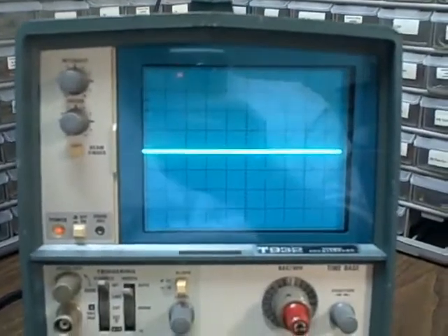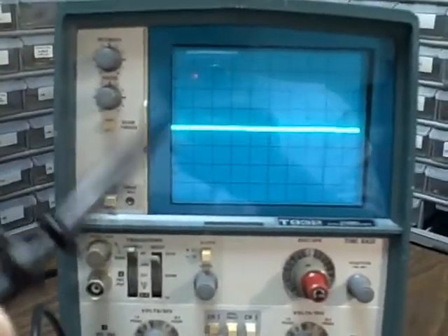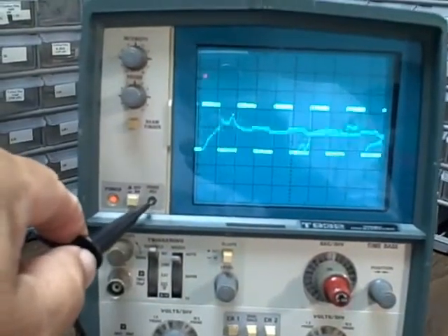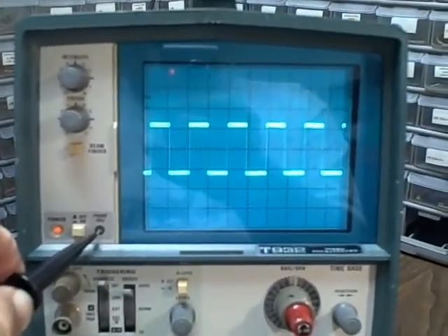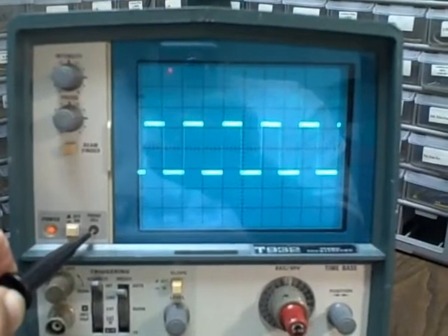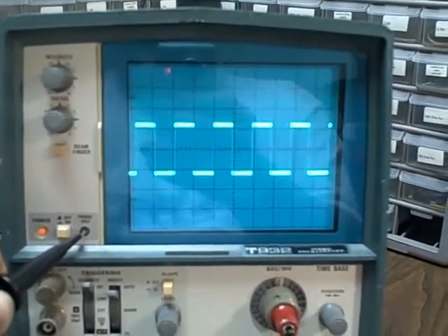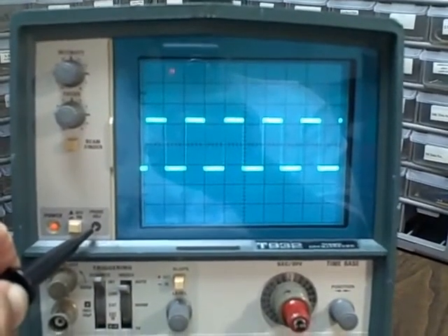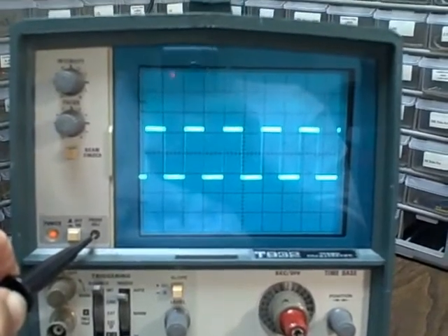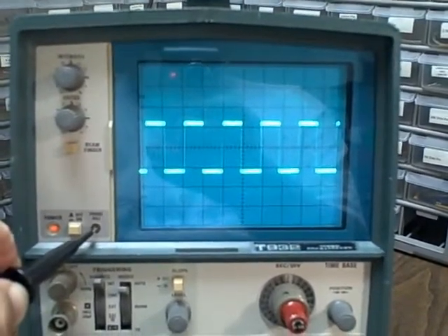Okay, just going to show you that the calibration point works. I've got my probe ready, and we're on the calibration point, and we can see that we do indeed get the signal as we'd expect to get. So you can calibrate your probes.